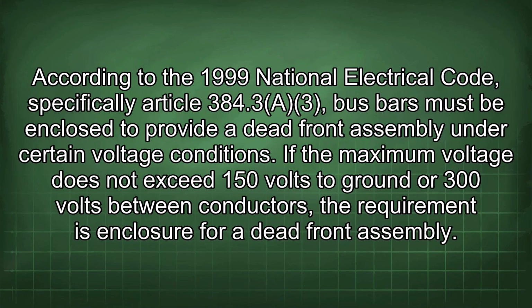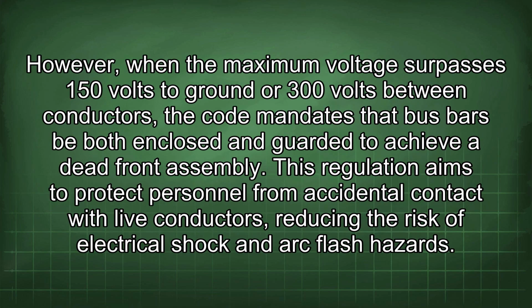According to the 1999 National Electrical Code, specifically Article 384.3A3, bus bars must be enclosed to provide a dead front assembly under certain voltage conditions. If the maximum voltage does not exceed 150 volts to ground or 300 volts between conductors, the requirement is enclosure for dead front assembly. However, when the maximum voltage surpasses 150 volts to ground or 300 volts between conductors, the code mandates that bus bars be both enclosed and guarded to achieve a dead front assembly.